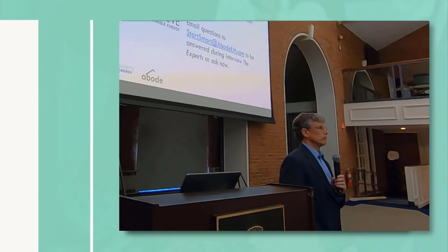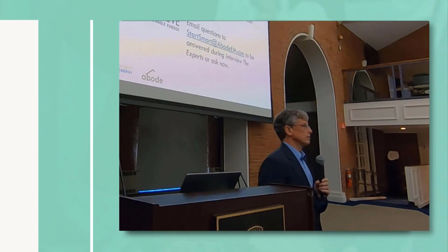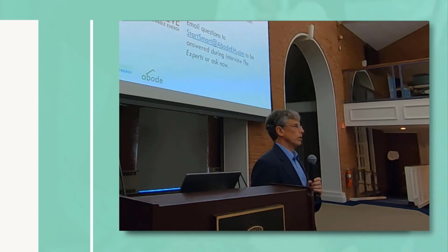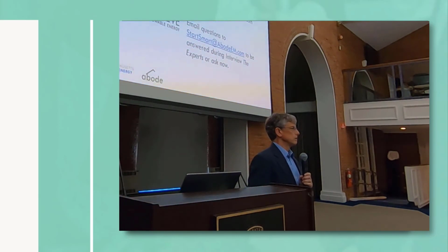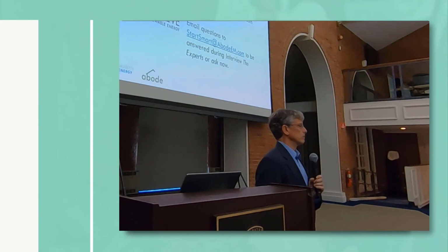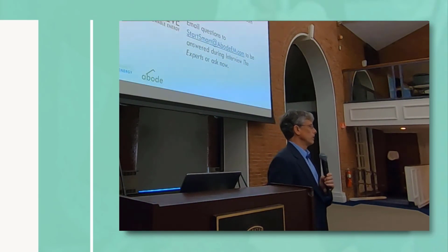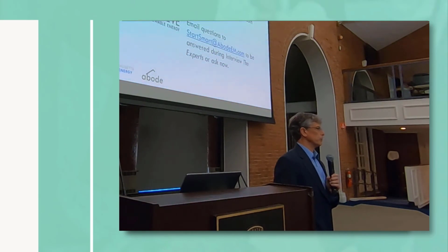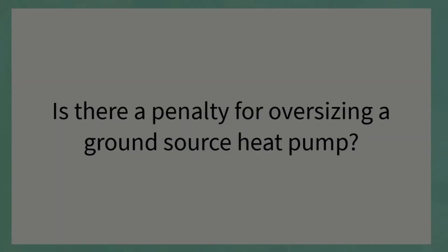600 feet of drilling is 1,200 feet of pipe, plus whatever the offset is into the house. An equivalent slinky system is going to be 2,400 linear feet of pipe at least, plus the offset. But your trench is, yeah, so how many linear feet? 100 feet by 3 for 1 ton of slinky is the usual rule of thumb without having thought about any of the geology or how deep it's going to go and that sort of thing.